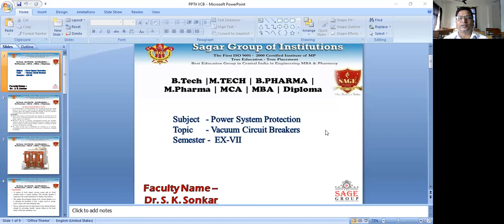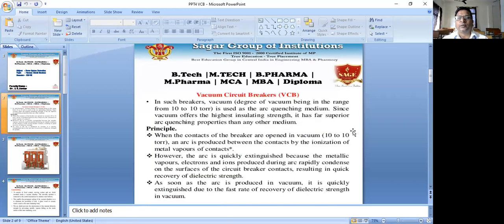Today we are discussing the vacuum circuit breaker. The vacuum circuit breaker, VCB, is also called a vacuum breaker. A degree of vacuum in the range of 10 to 10 torr is used as the arc quenching medium. Since vacuum offers the highest insulating strength, it has far superior arc quenching properties than other mediums. So vacuum is used as the arc quenching medium.